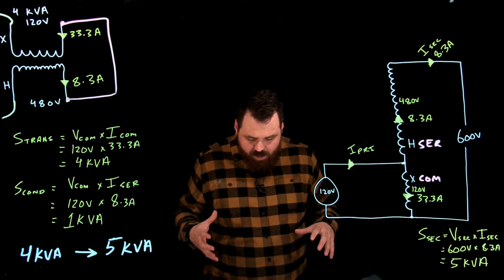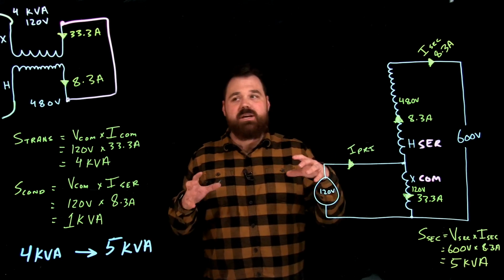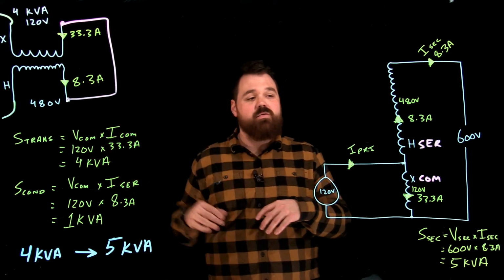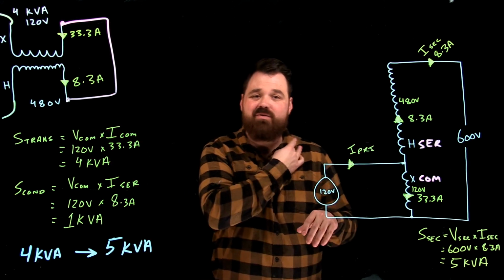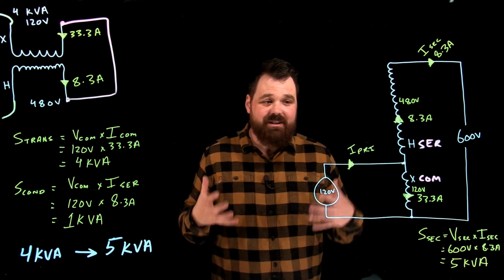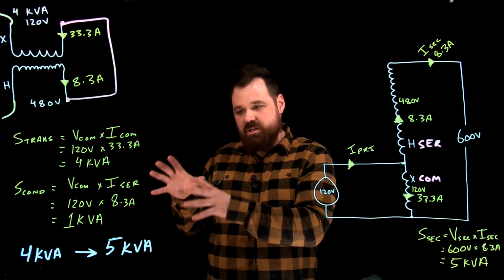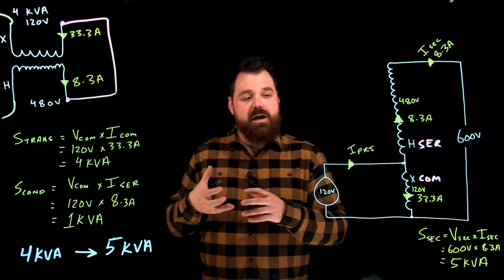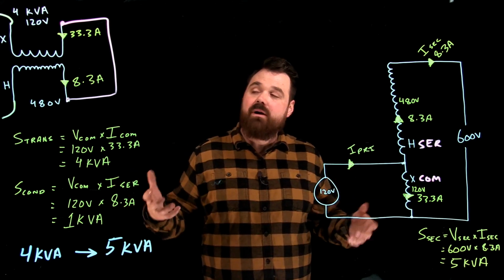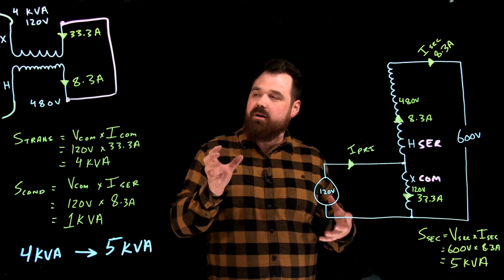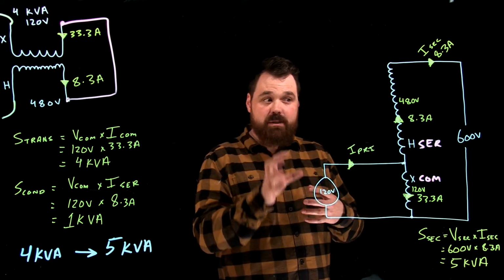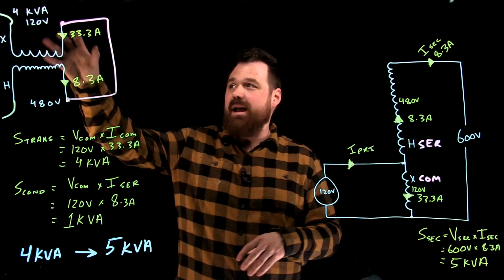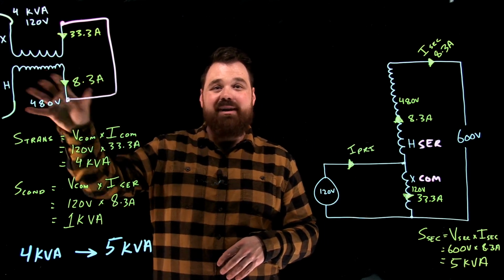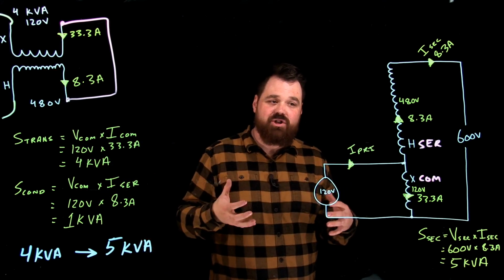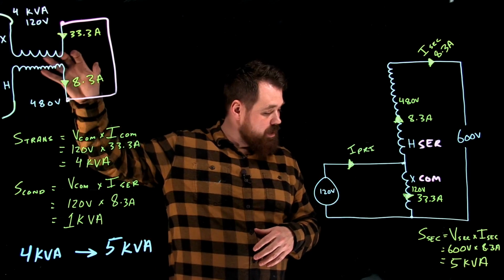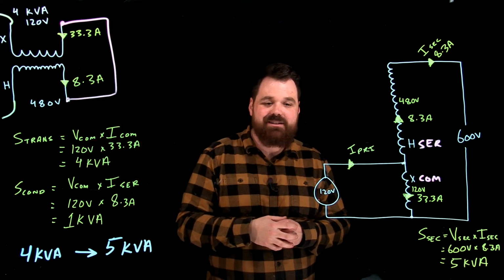So that's the concept of taking a mutual induction transformer and converting it into an auto transformer. Again, it's not something we're likely going to see or do except for maybe an emergency or a very special, unique case. But the theory behind it is very cool. And what I like to emphasize here is really the windings themselves, the rating of the individual X winding and the rating of the individual H winding, those ratings do not change. The voltage rating stays the same and the current rating on those stays the same.